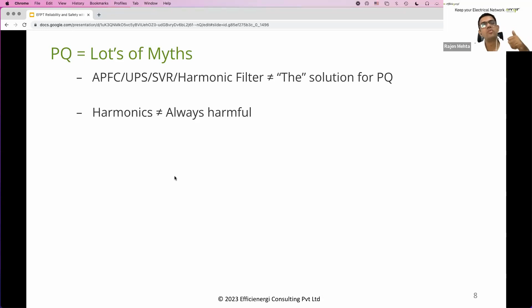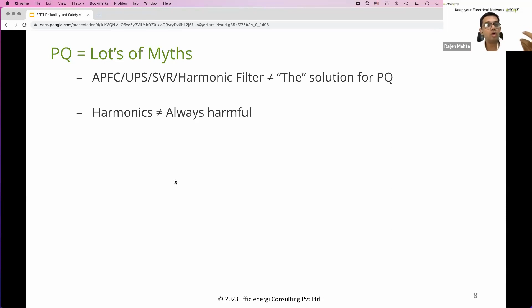An oversized system is not always better for power quality. We have quite a few designers who will oversize systems in terms of sizing of breakers, cables, and so on. But it can be detrimental in the real practical sense when it comes to downtime tripping events, or having a motor which is inefficient because of its oversizing. So it's not always good to have an oversized system for better power quality. Yes, in the right places, for right sizing of cables or to consider derating of nonlinear equipment, I would appreciate it, but not always.